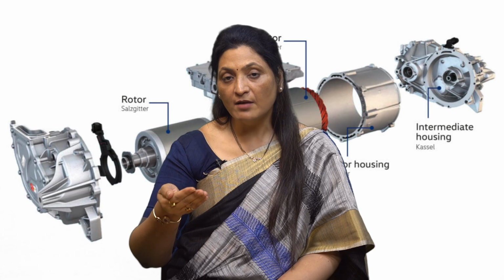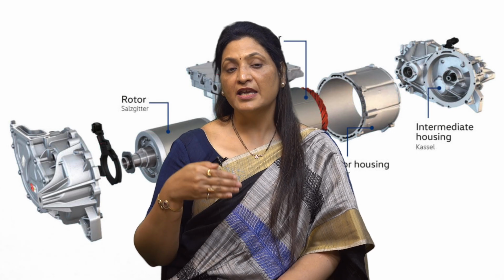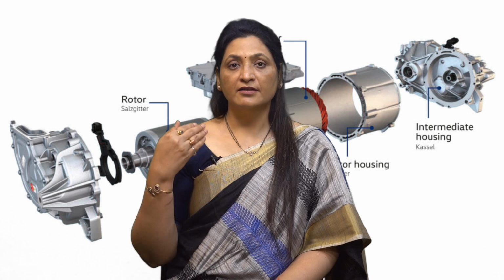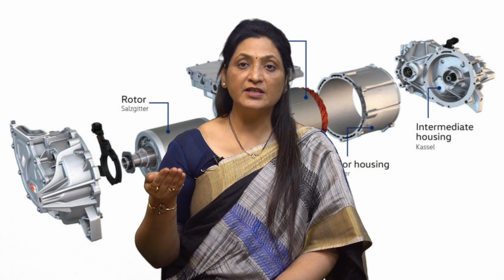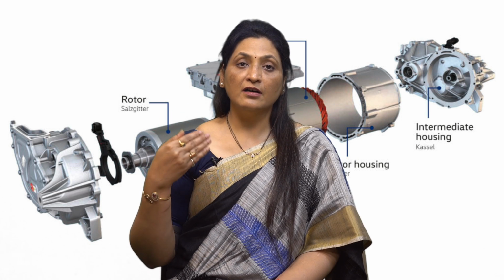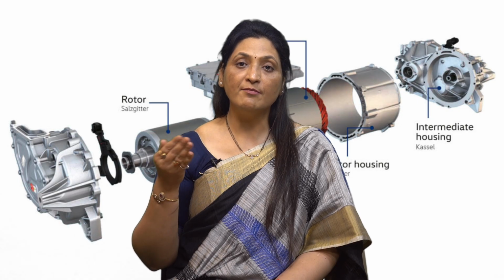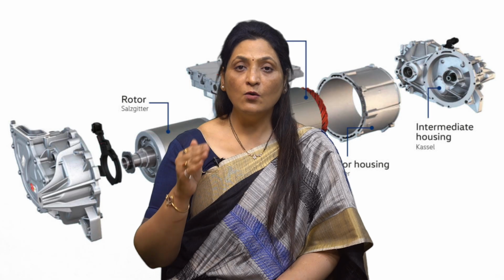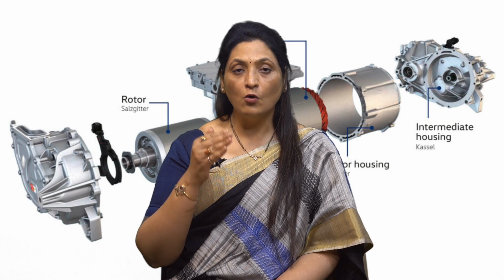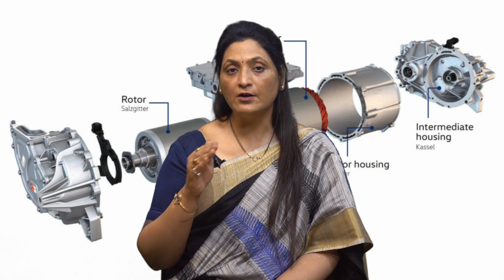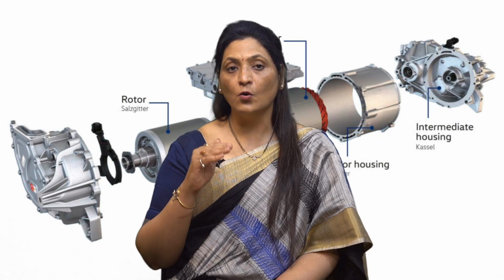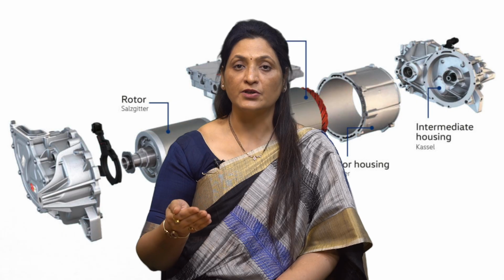The braking requirements from the load point of view: easy and effective braking are the requirements of a good drive. The starting torque is necessary for the load. The corresponding starting current drawn by the motor affects the selection of the drive. It is well known that running of motors with low power factor values is not at all economical, and the power factor varies with the load conditions in some motors.